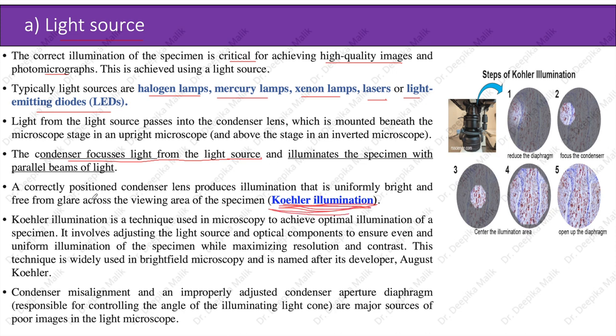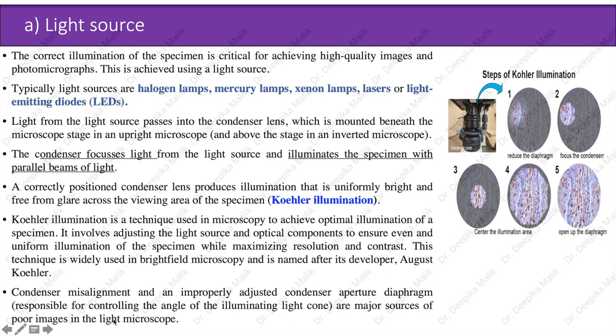Köhler illumination is a technique used in microscopy to achieve optimal illumination of a specimen. It involves adjusting the light source and optical components to ensure even and uniform illumination while maximizing resolution and contrast. This technique is widely used in bright field microscopy and is named after its developer August Köhler. Condenser misalignment and an improperly adjusted condenser aperture diaphragm — responsible for controlling the angle of the illuminating light cone — are major sources of poor images in the light microscope.